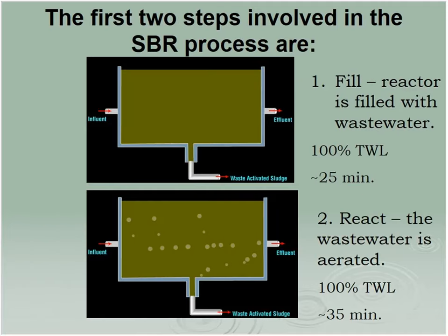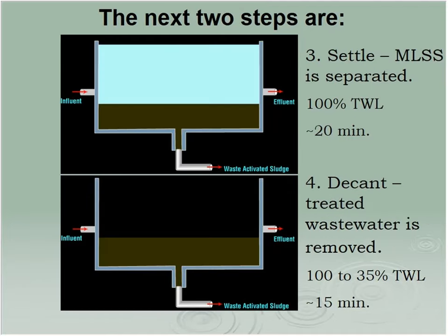So we've got a tank. Could be circular, could be rectangular. Tend to go with the rectangular, common walls. So we've got a fill, so we're going to pump water in, then we're going to aerate for some amount of time. When that time has been met, then we're going to kill the air, and now the tank becomes a clarifier. We let all the solids settle to the bottom. Basically a computerized version of fill and draw that was developed in the 19th century.